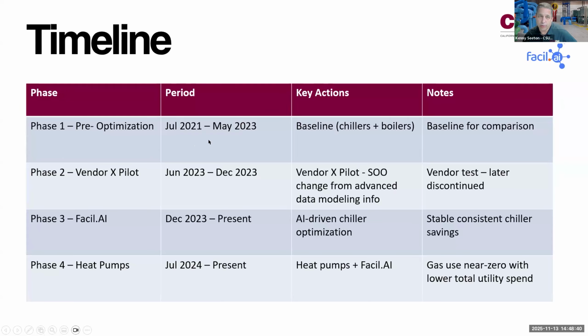Where we got there: we were just doing chillers and boilers forever. We tried out a different so-called AI vendor for about 6 months. It worked, but not to the extent that we needed it to. It wasn't consistent enough, and it didn't take everything into account. Then we tried out Facil.AI. It ended up giving us really stable, consistent chiller savings, and we can see those in a minute. And then we added the heat pumps, so it kind of skewed some of the savings numbers, right? Because you can't do all these different things and it's hard to model, but I've got some data that will show you where that goes.